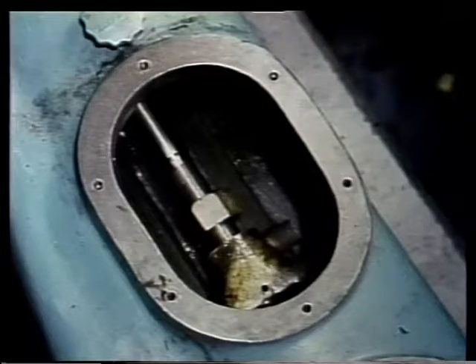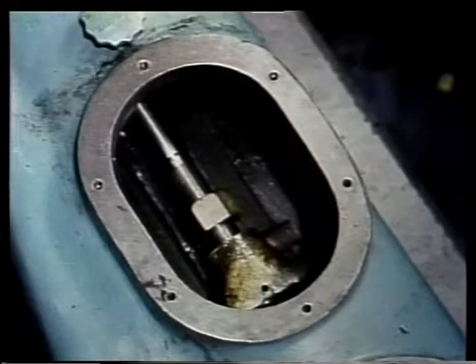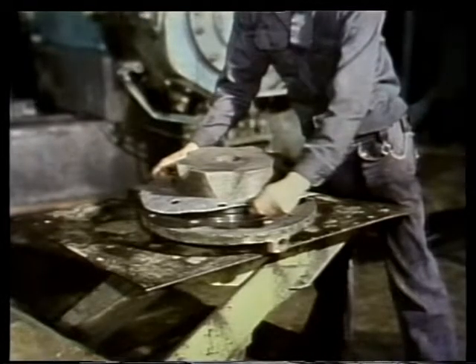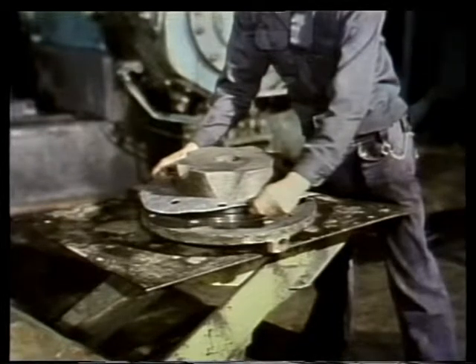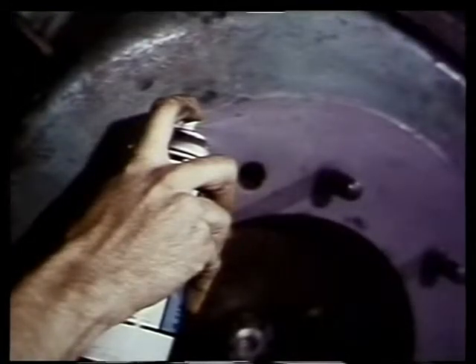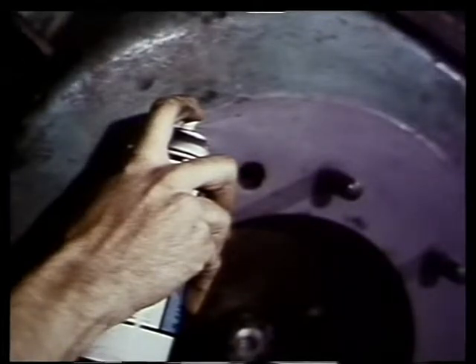Now you can put the head back on the cylinder. Again, a portable table is needed to help support the weight of the head. Don't forget to put on a new gasket. Spray a lubricant on the head seating surface first to help prevent the gasket from sticking the next time the head's removed.